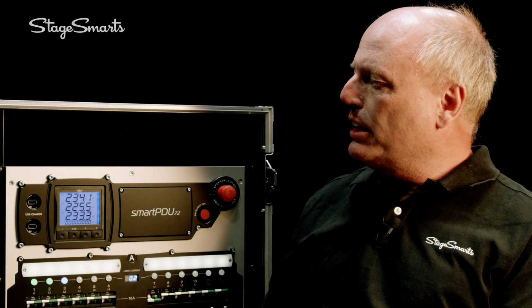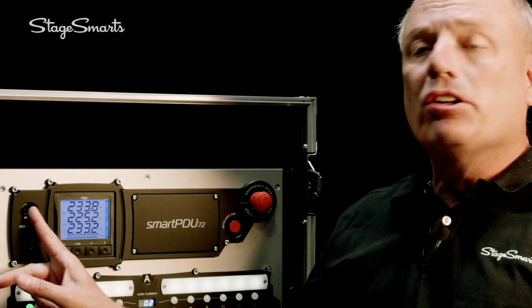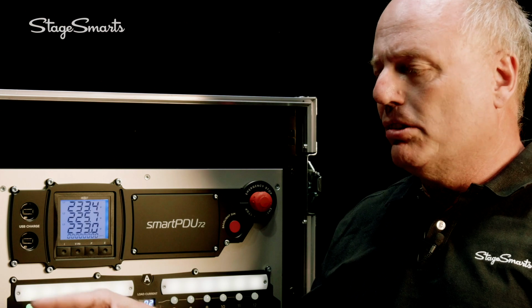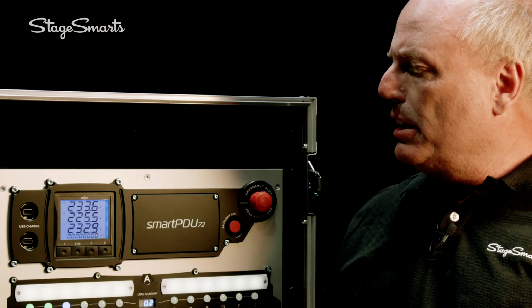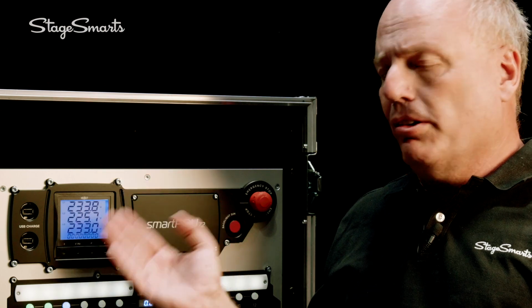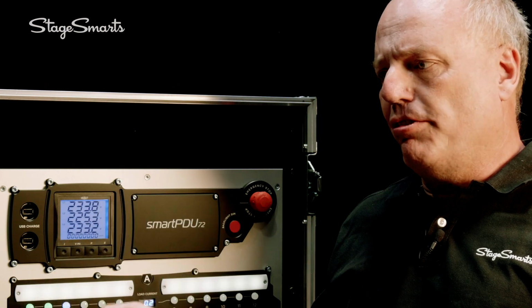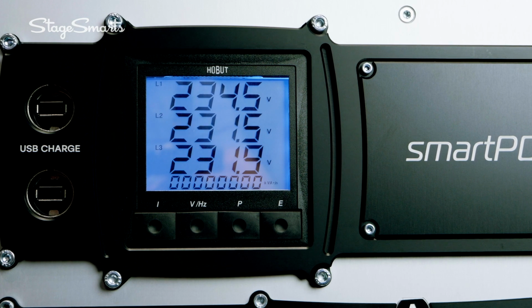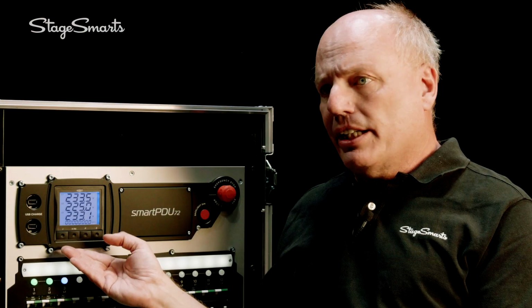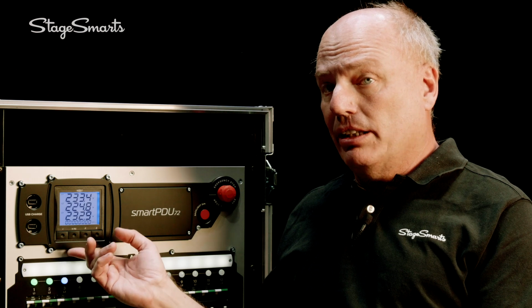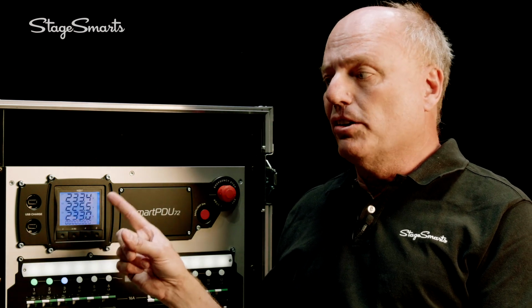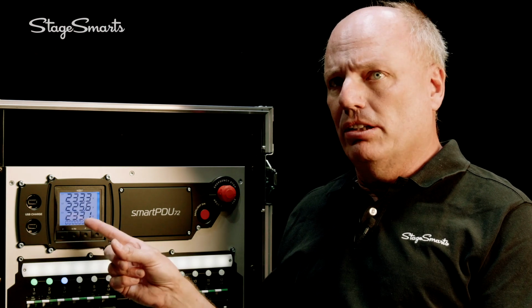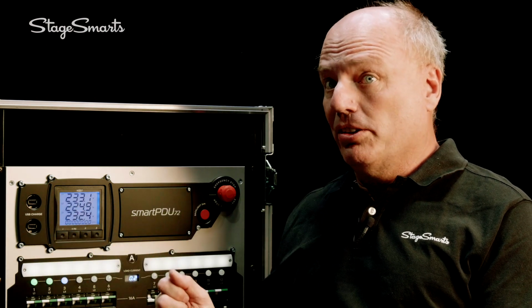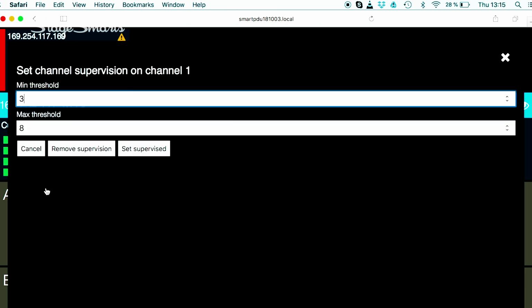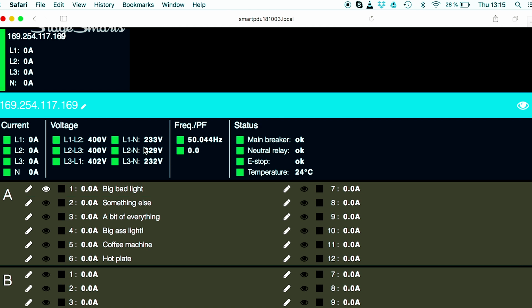Starting on the left side here, we actually have two USB charge ports. Just for convenience, you can power your iPad, your iPhone, your whatever. Next to this, we have the main incoming meter. This checks all the incoming voltages, currents, frequencies, power factor, everything. We've sourced a meter that is able to take a misconnected incoming power. So this is actually put before the main breaker. So if you have a miswired incoming power, you notice before you turn on the rack. And all of this information is also available remotely via our web application. Anything with a browser can check all this data.